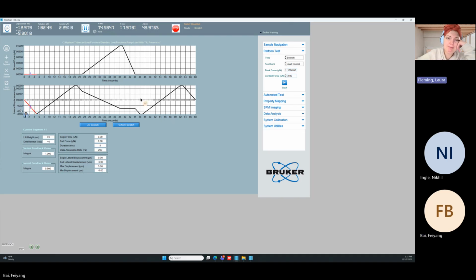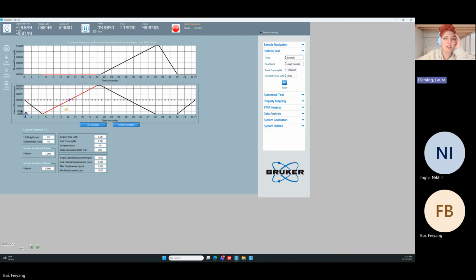Yes, this last segment, this part. Basically, if you don't have retrace, that part doesn't exist, right? You just do the little pre-scratch, you do your actual scratch, and then you're done. With tilt, it only has this first part where it traces. So in that first part, it's tracing over the sample surface to see the normal displacement change as a function of the lateral displacement so that we can correct for it, right? Then this is where the actual scratch occurs, either with a ramping load or with a constant load. And then that's where this one ends. Basically, you unload and you come back to zero. This is it just coming back to zero in both the normal force and the lateral force.